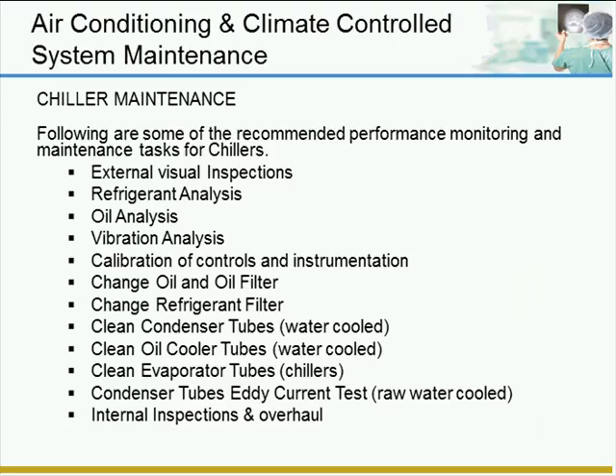The maintenance on a chiller system may include daily and weekly inspections. You want to monitor the temperatures and pressures, do semi-annual oil and oil filter changes, and then the annual maintenance: eddy current testing on the tubes, refrigerant analysis, oil analysis, vibration analysis, and calibration. You may want to change out your refrigerant filter. Cleaning of all the condensers and evaporators should be an annual thing, if not a monthly thing. You want to remove all the debris and make sure everything's structurally sound. Every 5 years, you might have a complete overhaul, depending on how often the unit runs.